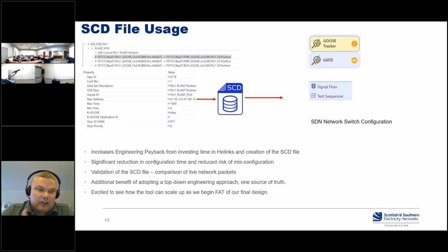And I like to say that it gives more engineering payback. If you put the time into designing, investing the time in your SCD file and SCD engineering, then you get a lot more payback from it in terms of being able to use it for your testing if these applications can consume it without user input. We also actually use the SCD file now to configure our network switches, which is another added bonus and payback from that. So that contributes to a significant reduction in configuration time.